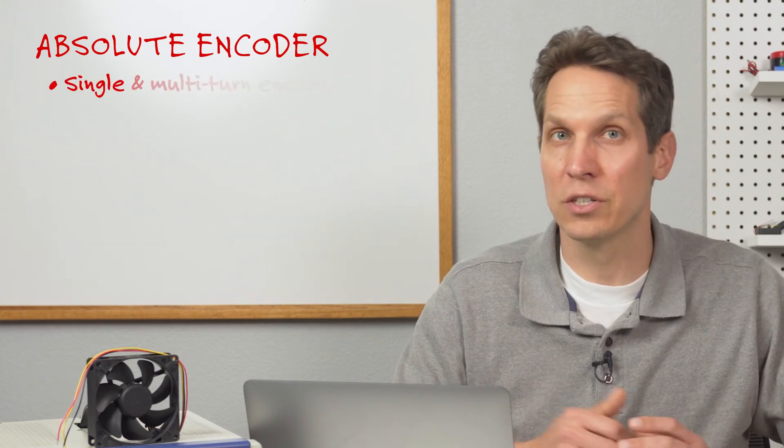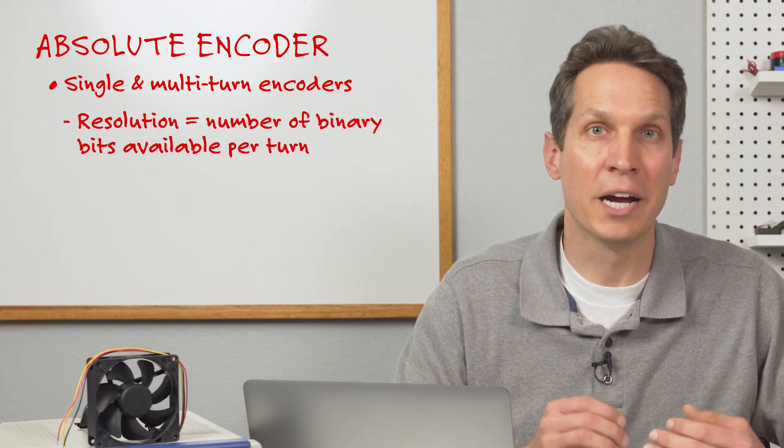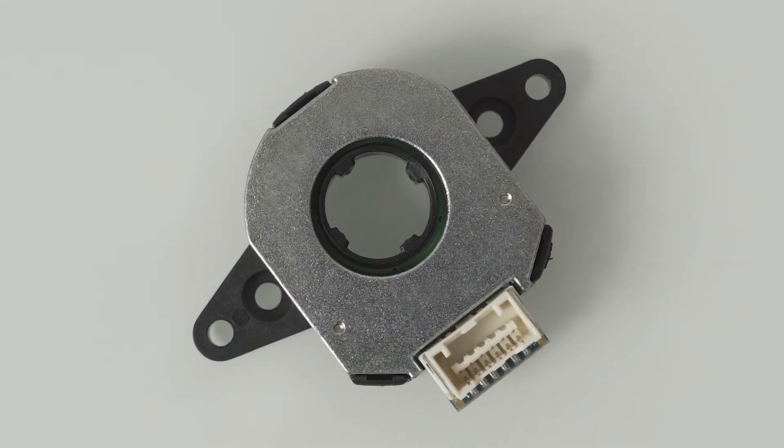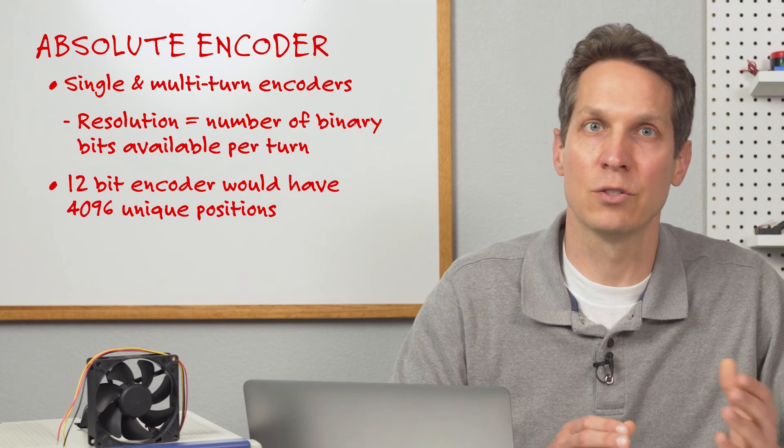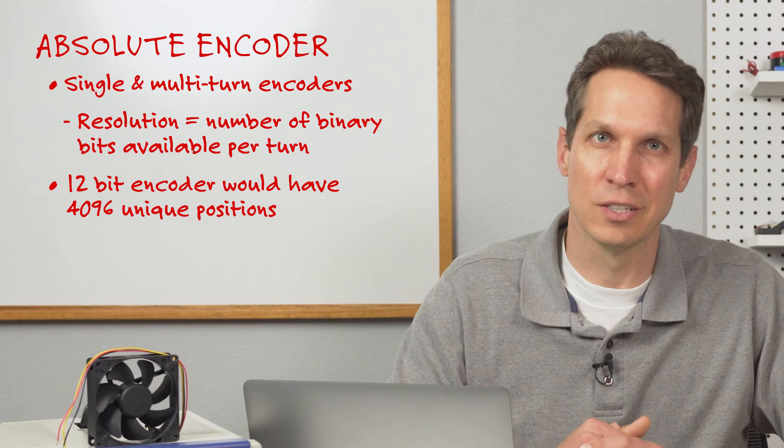For both single and multi-turn encoders, the resolution of these sensors is usually specified as the number of binary bits available per turn. For instance, a 12-bit encoder would have 4096 unique positions similar to the number of states in the 1024 PPR, or 4096 CPR, incremental encoder described earlier.